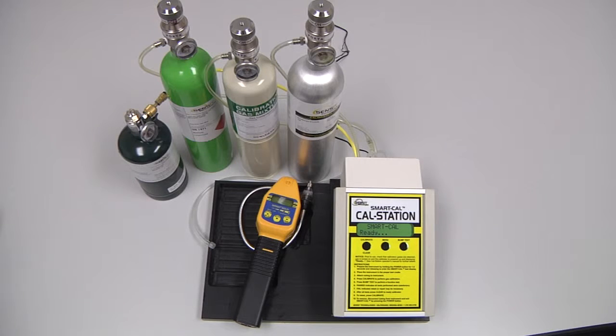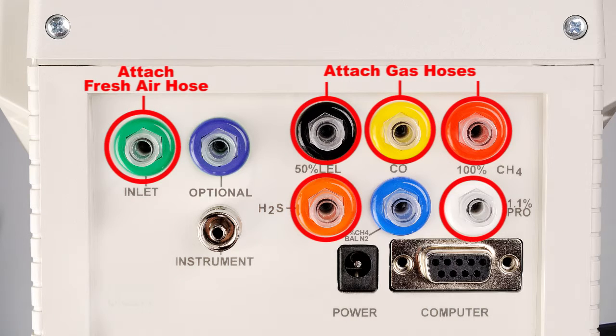and 100 parts per million carbon monoxide attached to both the black and yellow inlet of the cal station through a Y adapter. A bottle of 25 parts per million hydrogen sulfide attached to the orange inlet, a bottle of 100% by volume methane attached to the red inlet, and if this instrument were set up for propane, we would need a bottle of 50% LEL propane attached to the white inlet.